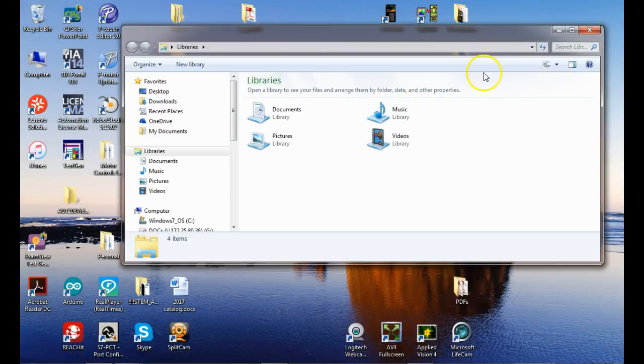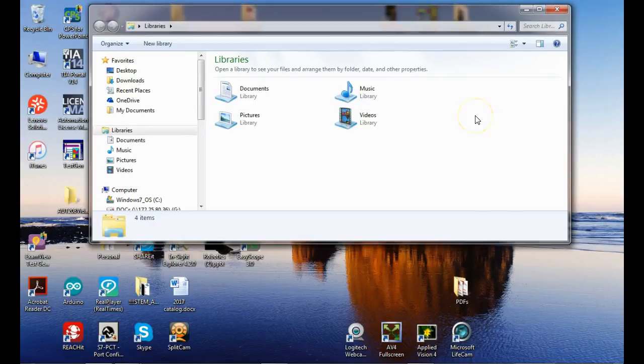One shot is something we're going to have to look at today. A one shot is a digital device that when you energize it, it gives you one shot. So the output becomes true for one shot, and then it goes back what? False. So you can leave it true the rest of the time. It makes no difference. It gives you one shot on the output. To make you get another one shot, what would you have to do? You have to de-energize it first and then do what? Re-energize. So I knew that one we need to understand because, when we look at the Allen Bradley RSLogix 500 program, several of the ladder diagrams use one shots.